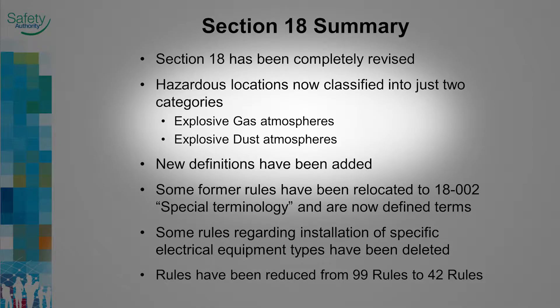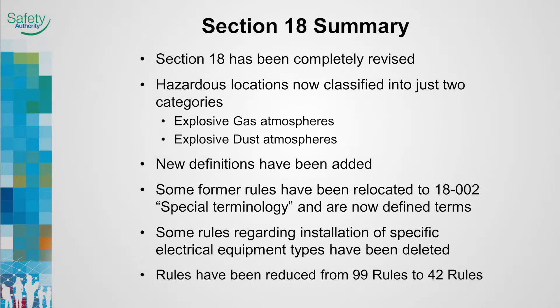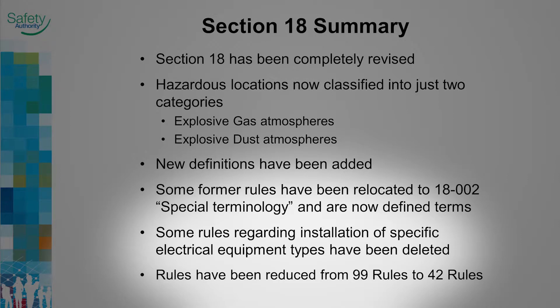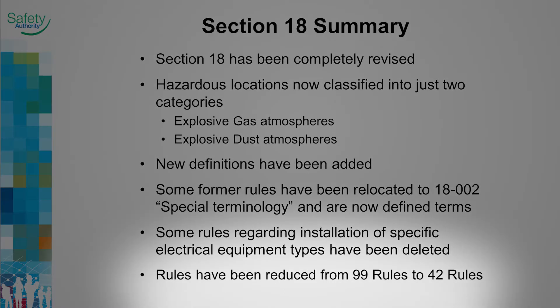Hazardous locations are now classified into just two categories: Explosive Gas Atmospheres and Explosive Dust Atmospheres. New definitions have been added; some former rules have been relocated and are now defined terms. Some rules regarding the installation of specific electrical equipment types have been deleted. The rules in Section 18 have been reduced from 99 to 42 rules.